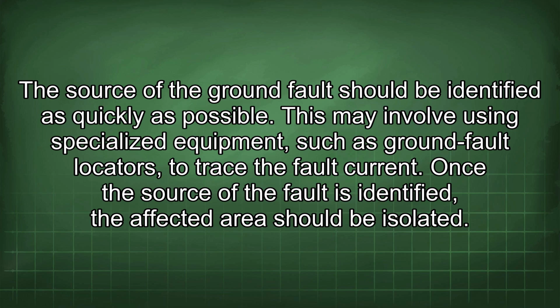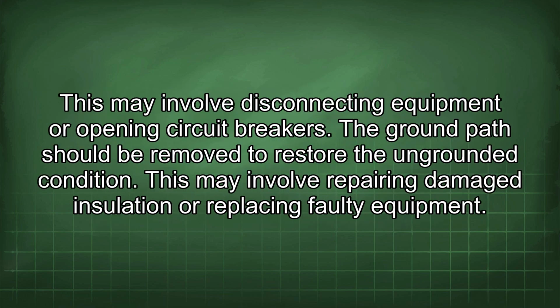This may involve using specialized equipment, such as ground fault locators, to trace the fault current. Once the source of the fault is identified, the affected area should be isolated. This may involve disconnecting equipment or opening circuit breakers. The ground path should be removed to restore the ungrounded condition. This may involve repairing damaged insulation or replacing faulty equipment.